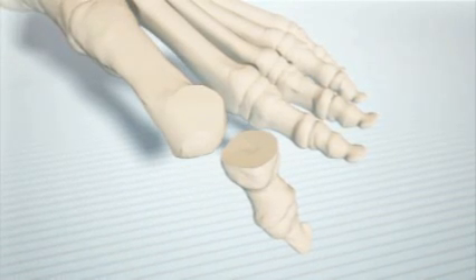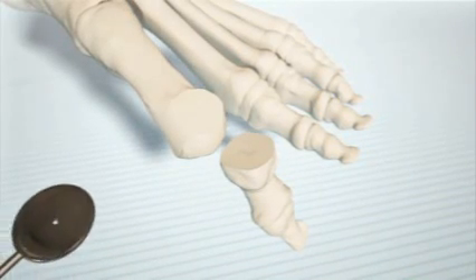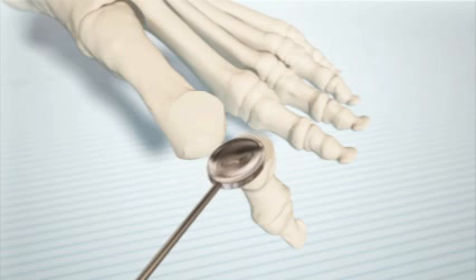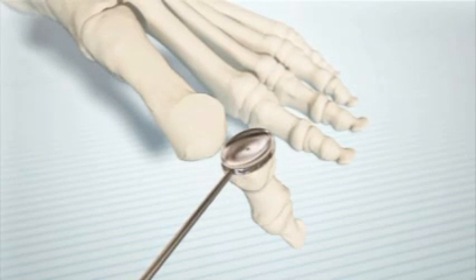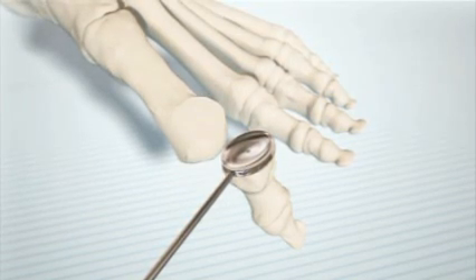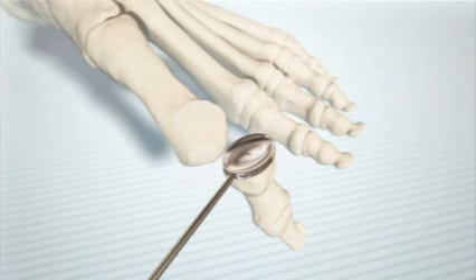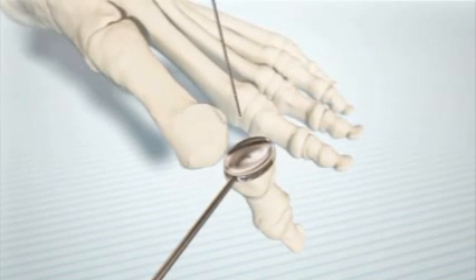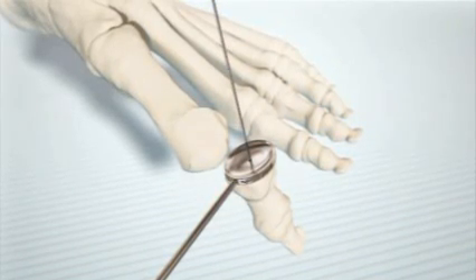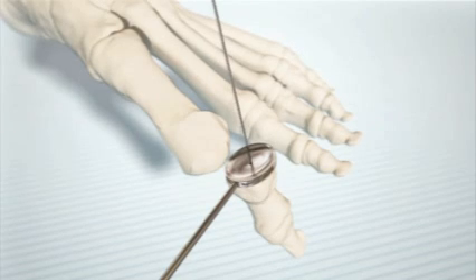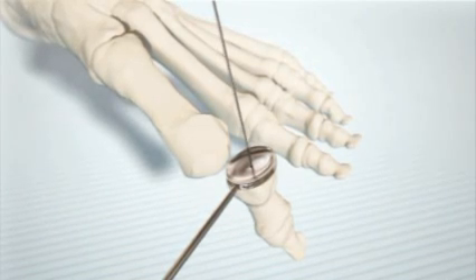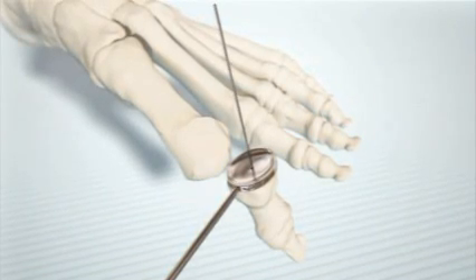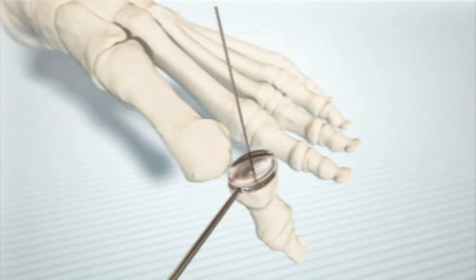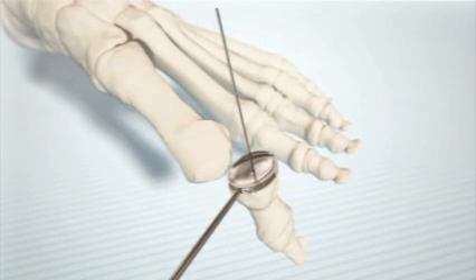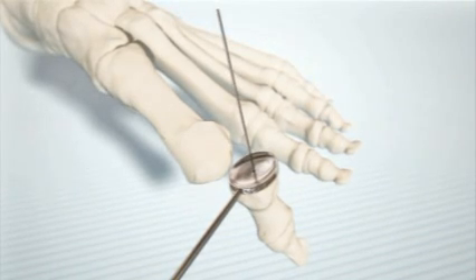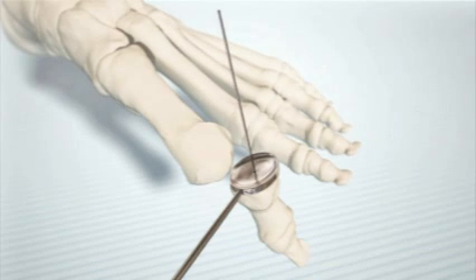Select one of the elliptical trial sizers and place it over the exposed surface. The implant should cover as much of the surface as possible, with little or no overhang. Once the correct size is selected, run a K-wire through the cannulated sizer. Advance the wire about 15 millimeters into the phalanx and observe how the sizer is seated. It is advisable to use a C-arm to make sure the wire is properly centered. If the wire is not properly positioned, remove the wire and reposition it.